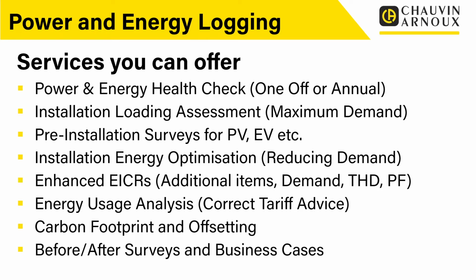Can we put timers in? Could we put thermostats in? Is there some level of automation we can add? Have we got the heaters coming on at the right time, varying over the year so they're not coming on unnecessarily? Have we even got lighting switched properly? There's examples where lighting near windows can be switched off while that further from the windows stays on, so you might have two light switches for a room where you'd previously have had one.